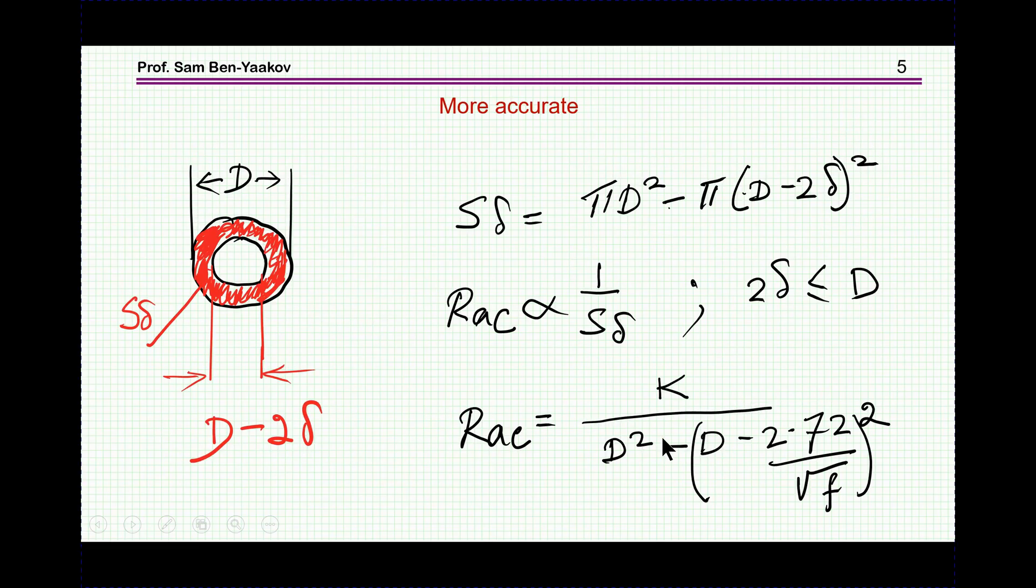Now, there is a more accurate way to estimate the RAC, and that will be to actually calculate more accurately this area here, this belt here. And this will be done by taking the total area, and subtracting from it this inner circle here, inner area, the diameter of which is D minus 2 delta, because we have delta here and delta here, so this is D minus 2 delta.